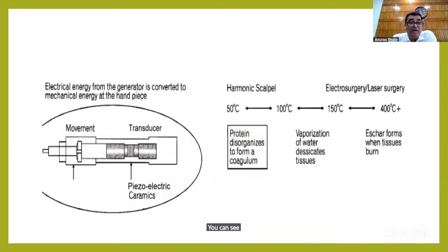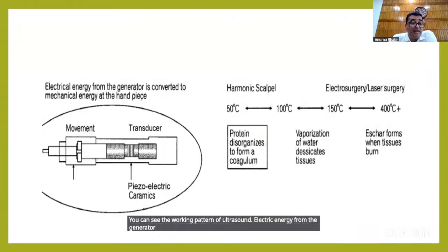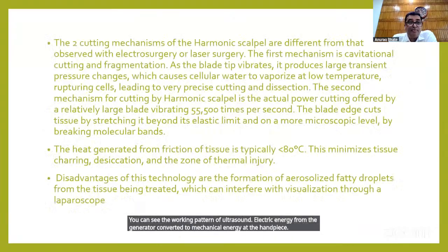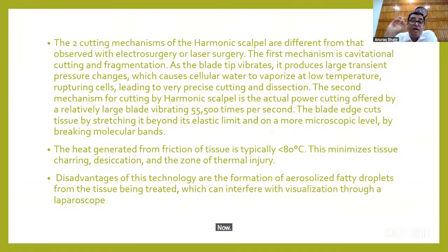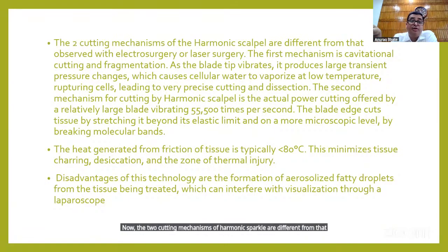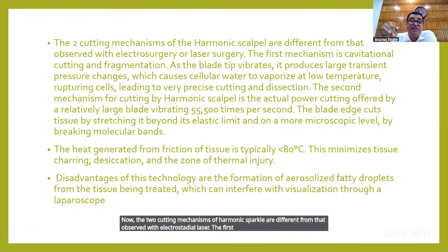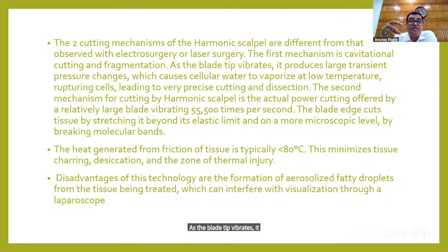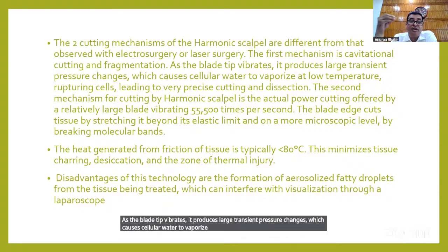You can see the working pattern of ultrasound. Electric energy from the generator is converted to mechanical energy at the handpiece. Now, the two cutting mechanisms of the harmonic scalpel are different from those observed with electrosurgery. The first mechanism is cavitation, cutting, and fragmentation. As the blade tip vibrates, it produces large transient pressure changes which cause cellular water to vaporize at low temperature, rupturing cells, leading to very precise cutting and dissection.